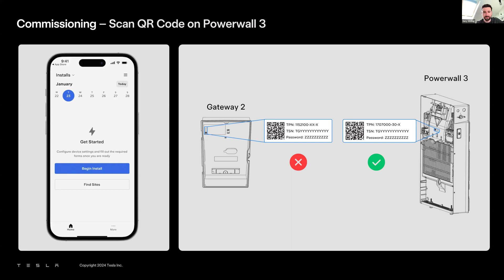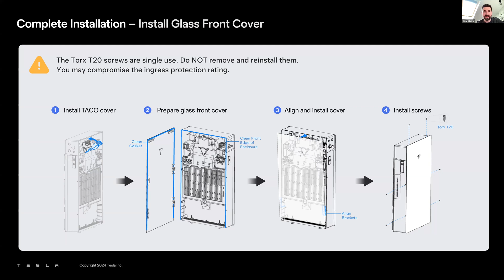Once it's all commissioned, the door goes on. Just remember the unit has a rainproof cover. What I like to say is don't wait till you're finished before you put it on, because if you're outdoors, you don't want to risk any rain getting in. So install the rain cover as soon as you open the unit. The door attaches with 6 T20 screws, 2 on top, 4 on the sides. Once it's all screwed up, it's good to go and you can go home for the day.